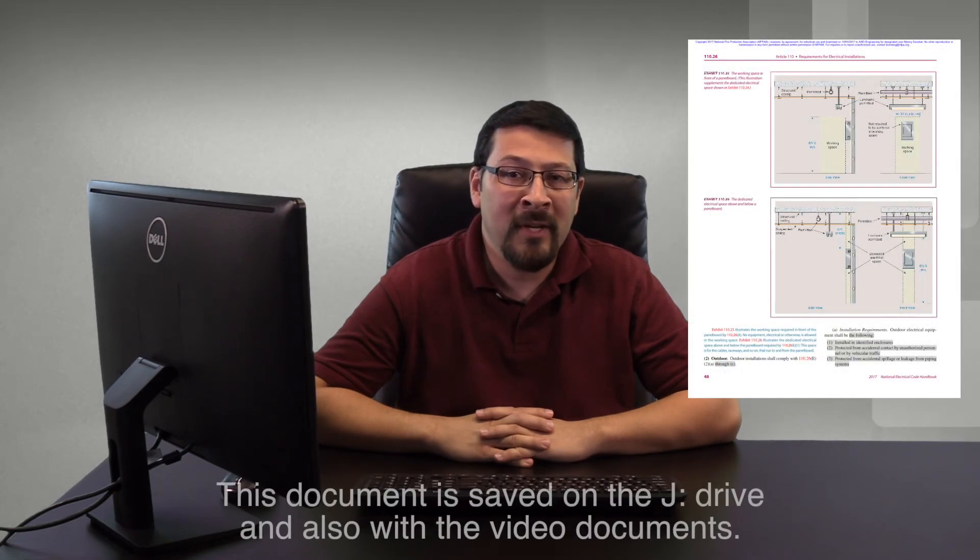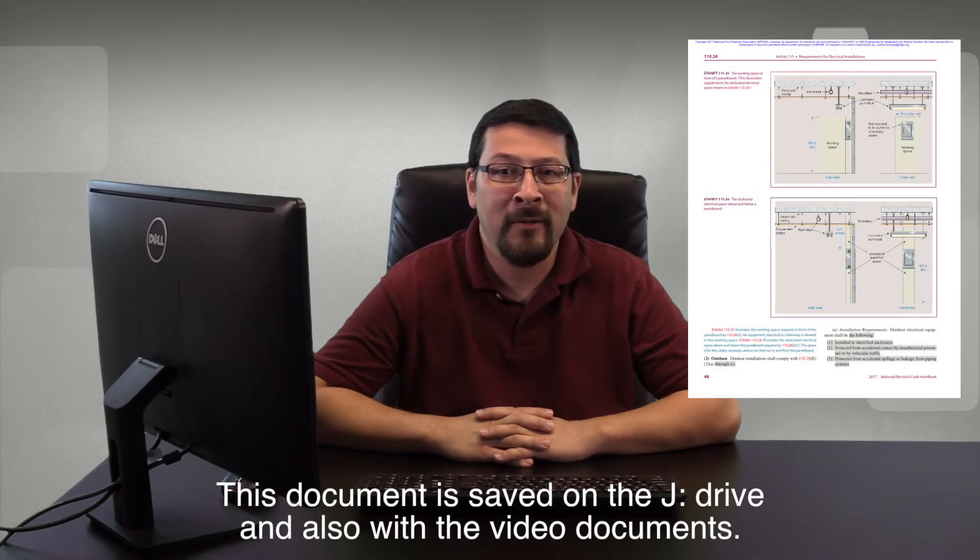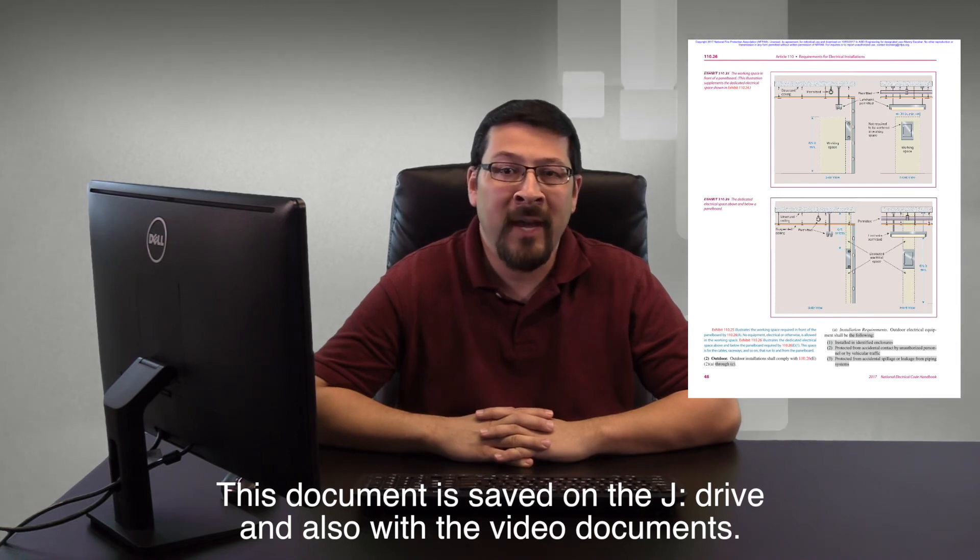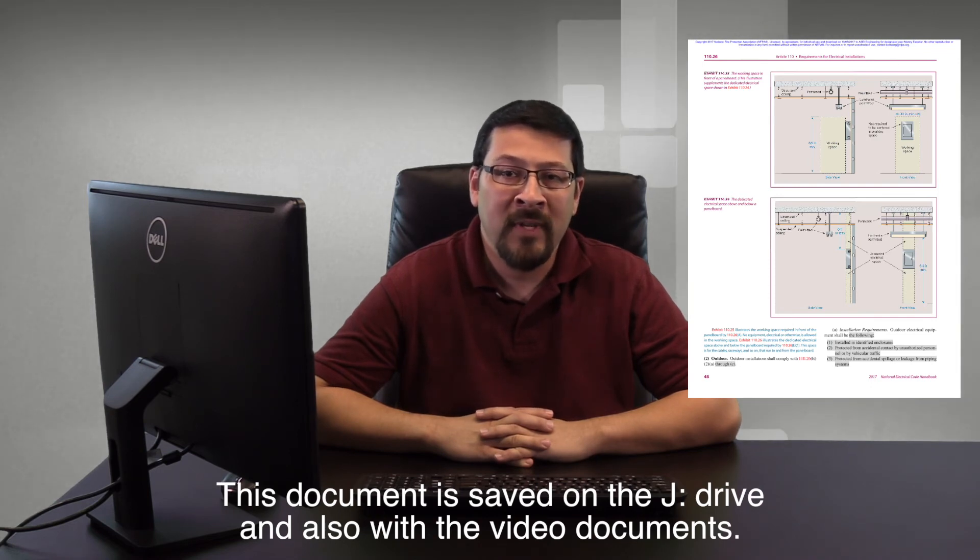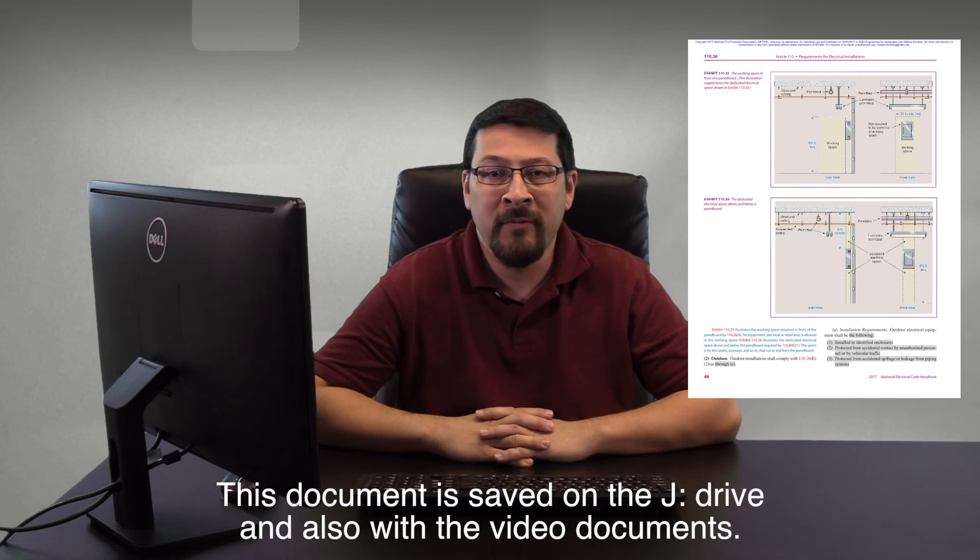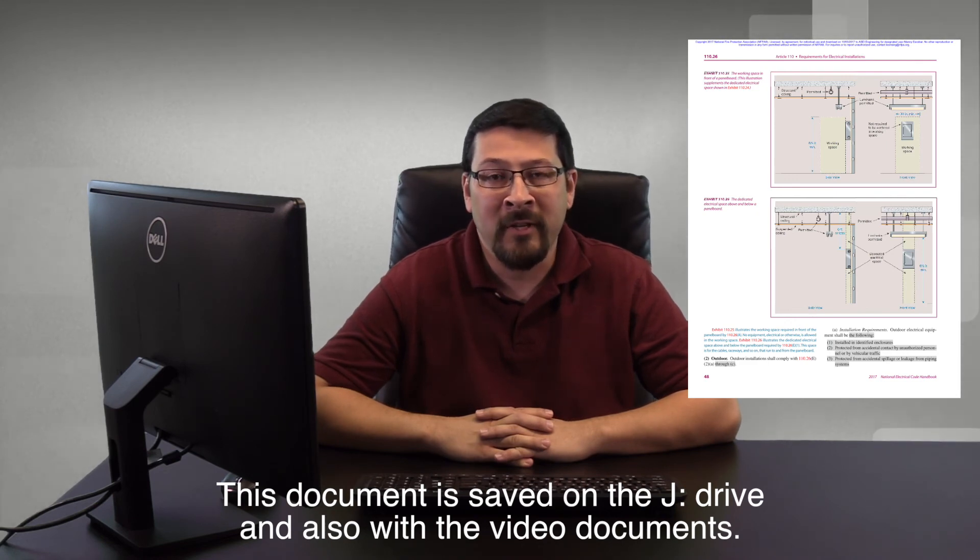Final notes. One, if you're not familiar with the local utility requirements for electrical rooms, you're going to find the SRP and APS design manuals in the J drive in their electrical folder. Two, all your clearance info can be found in the NEC article 110.26. I referenced clear working space previously. Remember that also includes space below and above the panel as well. See exhibit 110.25 and 110.26 on the screen for a quick reference.